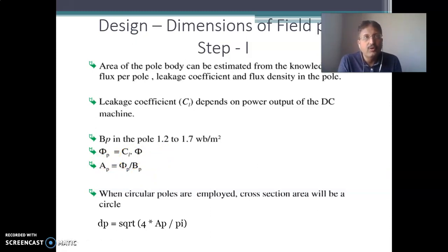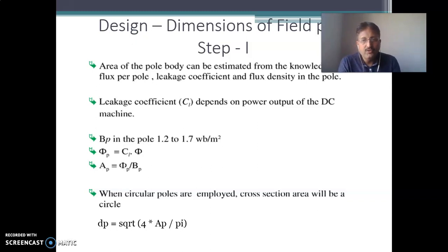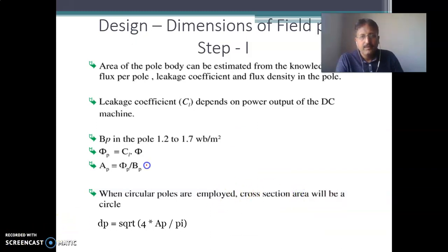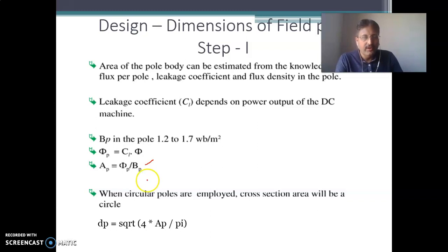Assume the flux density value in the range of 1.2 to 1.7 Tesla as per available data. Once you assume the flux density value, you can easily find out the area of the field pole — area equals flux divided by the assumed flux density. For circular poles, the area of a circle is (π/4)d², so you can find out the diameter as the square root of (4 × area / π).